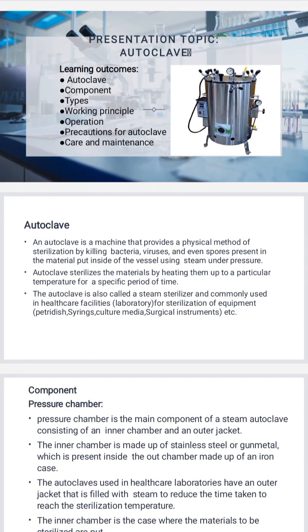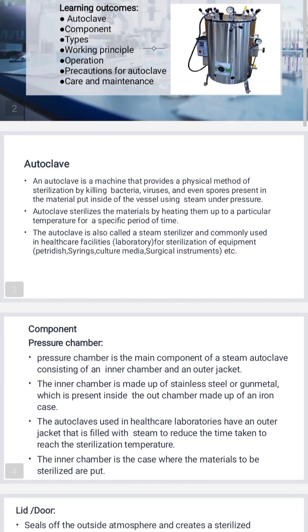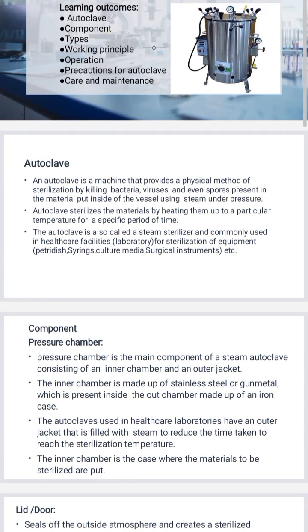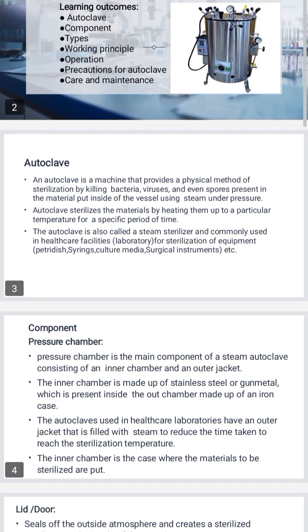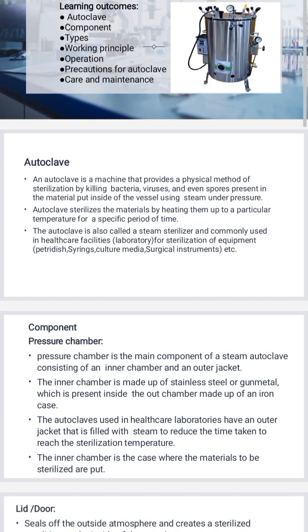Autoclave introduction. Autoclave is a machine that provides a physical method of sterilization by killing bacteria, viruses, and even spores present in the materials put inside of the vessel using steam under pressure. Autoclave sterilizes the material by heating them up to a particular temperature for a specific period of time. The autoclave is also called a steam sterilizer and is commonly used in healthcare facilities and laboratories for sterilization of equipment, petri dishes, syringes, culture media, surgical instruments, etc.